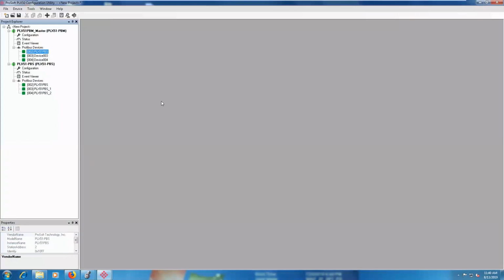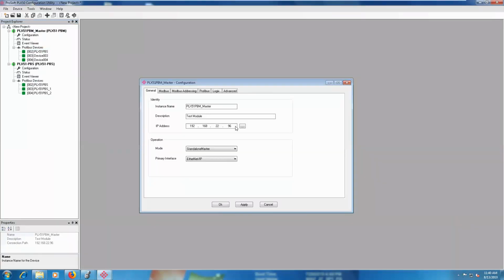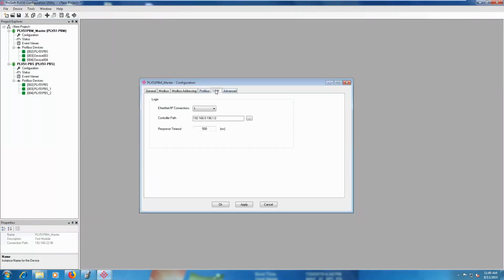So since we've got just a couple minutes here, I was just going to give you a quick introduction to the configuration software. The configuration software, like I mentioned, is our new PLX50 configuration utility. This is how you set up your Ethernet IP communications. You can configure your node ID on the network. You can configure the Logix device that you want to send status information to and the number of I/O connections that you need to support.